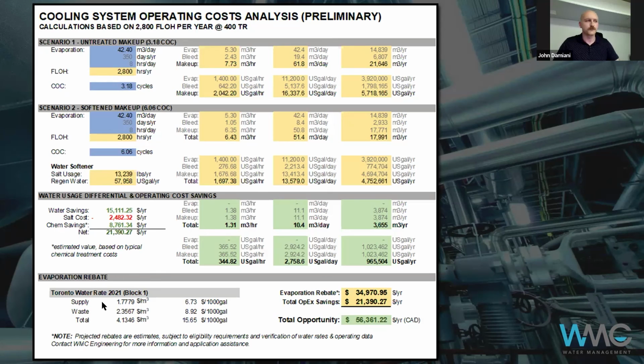So you've got that, and obviously other types of benchmarks too. If you're talking about premature failure, you've got corrosion rates you can measure. If corrosion coupon racks are installed in your systems and you're measuring corrosion rates, you'll get mils per year of corrosion. Once you reach a certain number of mils—meaning that much metal has been removed from the system—you're going to start having failures.